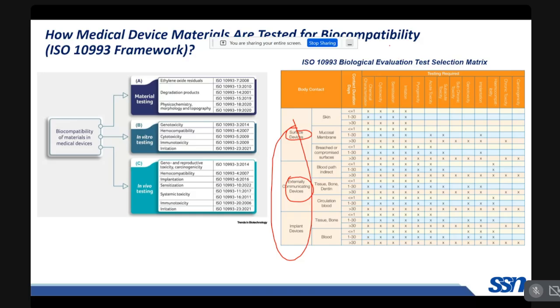Okay, so in addition to that, how long the device is in contact with the human body also determines what biocompatibility tests need to be performed. When it comes to, say, a stethoscope, this usually comes in contact with human skin, and the contact duration is less than 1 day. It is obvious that the doctor is not going to keep the stethoscope on the human body for more than 1 day. So if that is the case, cytotoxicity, sensitization, and irritation are the basic tests that need to be performed.